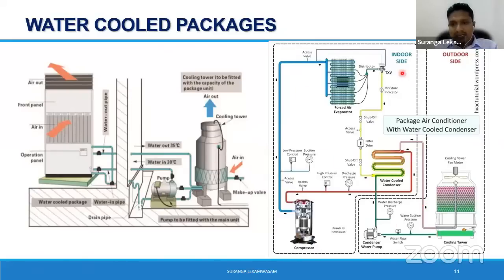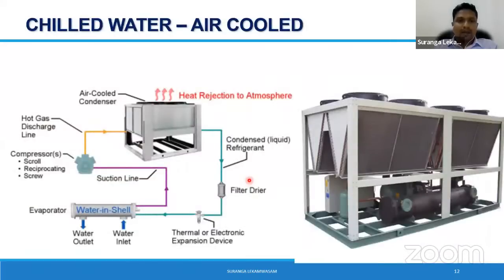For anyone interested, I have given you the circuit diagram on the right side. You can see they actually have a good heat exchanger known as a tube-in-tube heat exchanger, which is a fairly good heat exchanger. That is good, I mean, rather than relying on air-cooled systems, try to go for a water-cooled system because your overall efficiency improves. Well, then we have the chill water system.